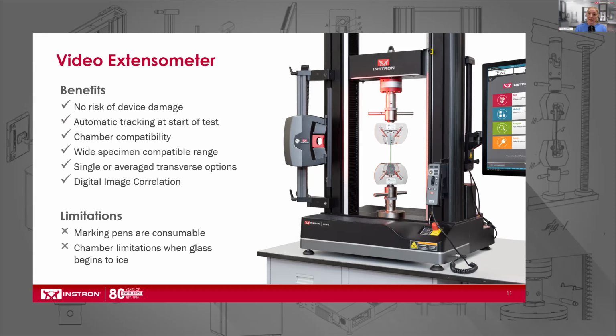Removing the need to retrieve the device and the ability to track through failure is also helpful for customers testing in chambers. You can just let the test run its course. You don't have to deal with opening the chamber door, putting on your gloves, retrieving that clip-on, closing the door. It's just a much more streamlined workflow.